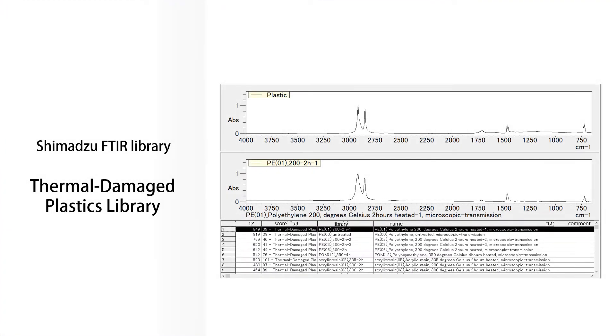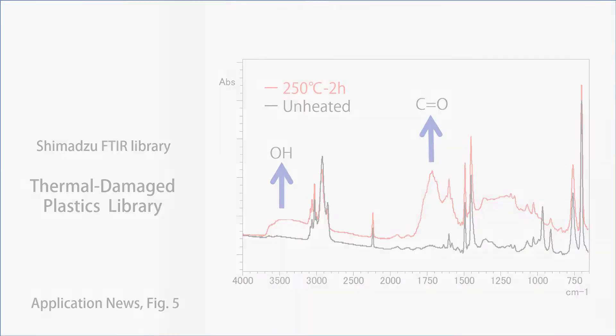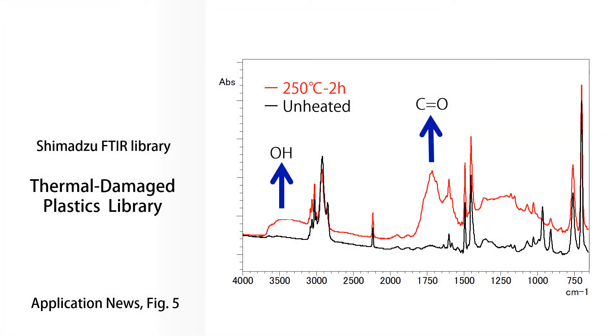To eliminate misidentification and lengthy training of operators, we present the Shimadzu-only Thermal Damaged Plastics Library. This library contains spectra data for 13 types of plastics in the unheated condition and when heated to various temperatures from 200°C to 400°C. It can be seen that the peaks of the OH group and C=O double bond appear when plastic is deteriorated by ultraviolet irradiation and heating. Let's see if we can actually detect the peaks of the hydroxy and carbonyl groups in a real sample, and if Shimadzu's library can correctly identify weathered microplastics.